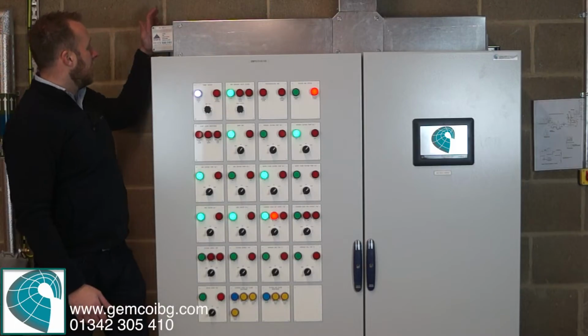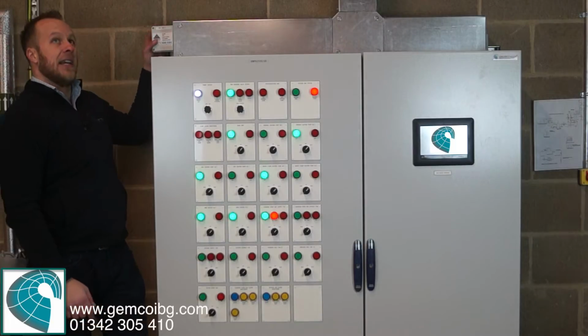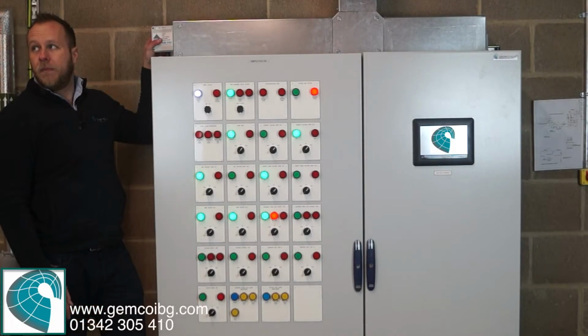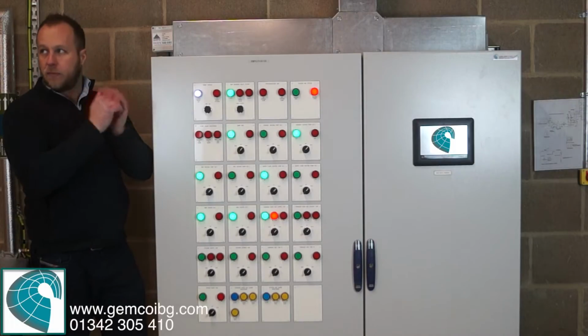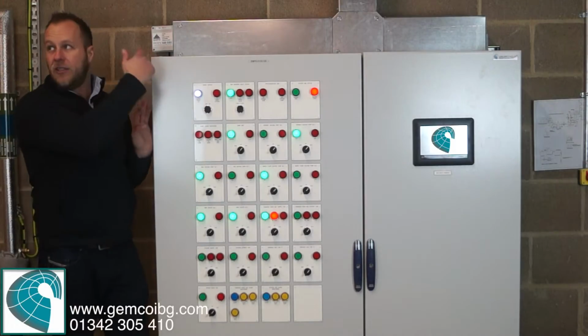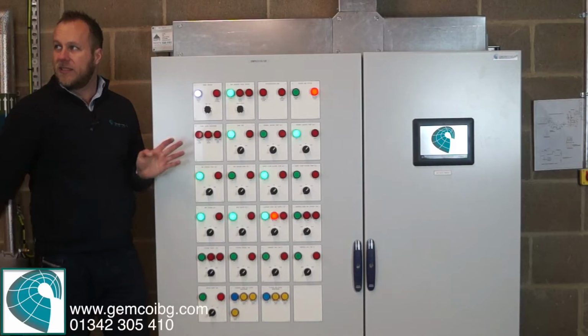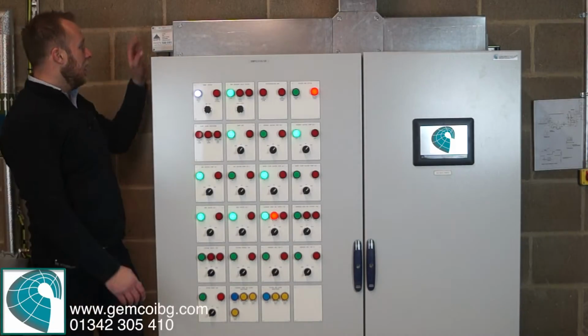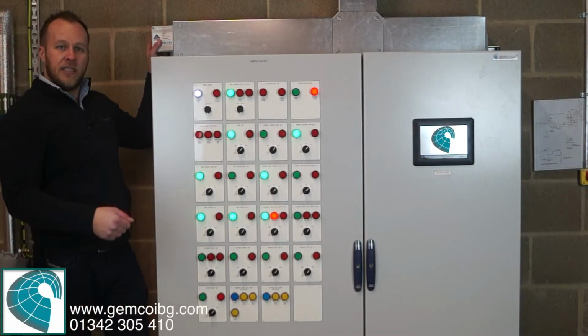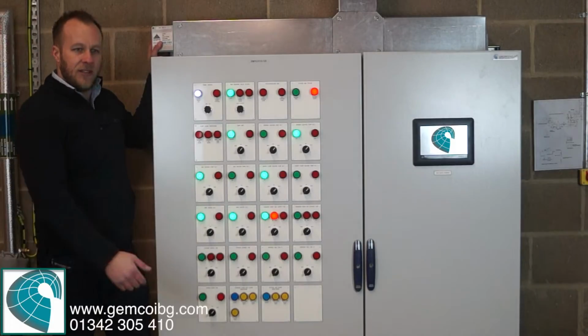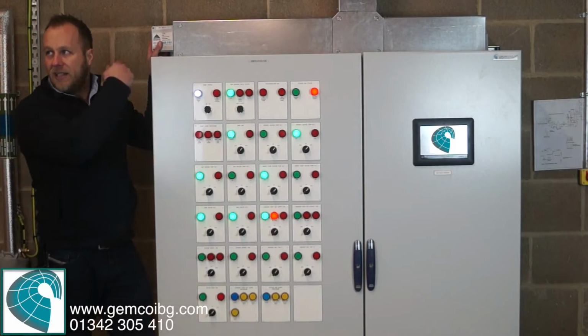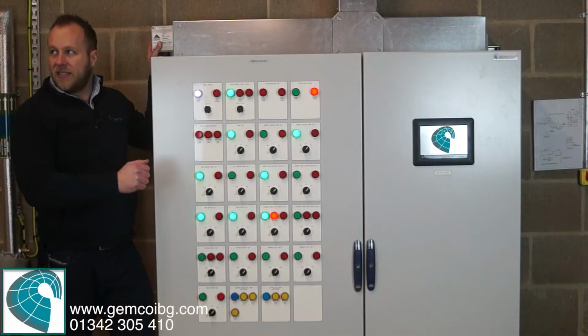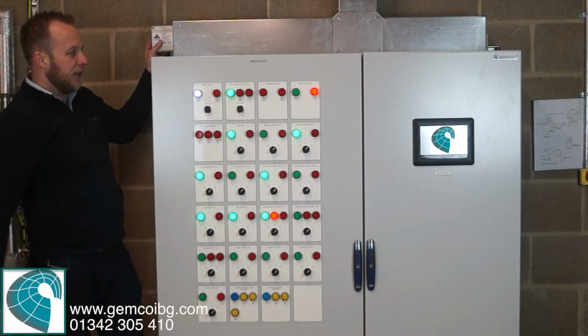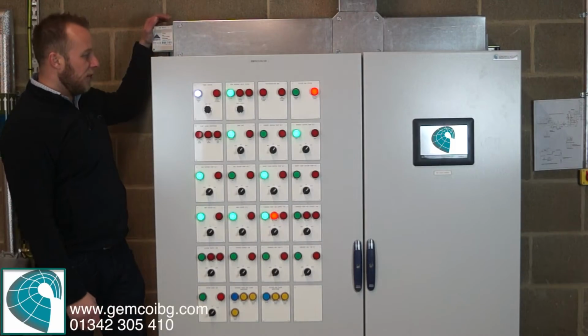The next lamp's the fire alarm. Above the panel here is a fire interface relay. That's wired into the fire alarm system. And when the fire alarm goes off, that will just break a contact, and this monitors that contact, and it breaks the circuit and says, shut down everything. Okay, so if you've got a fire alarm specialist in doing a test, and you don't want to shut all this down, you can probably ask him to isolate this loop just while he does a test, if you didn't want everything to go down. But that's the fire relay.